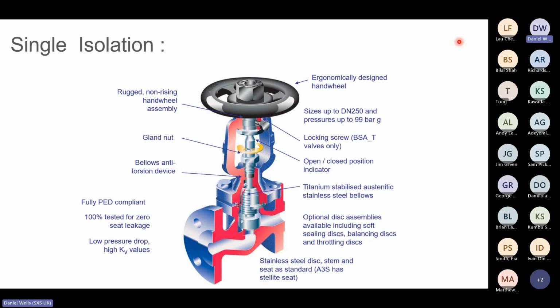But even when we've got a box fresh valve, even when it's fresh off the production line, it is only ever going to be capable of isolating with a 99.99 efficiency. So that means that it doesn't really matter what the condition of steam is. There is always going to be a risk that there's a very, very small amount of steam that is leaking across those valve seats because of the metal to metal, the highly polished surfaces.